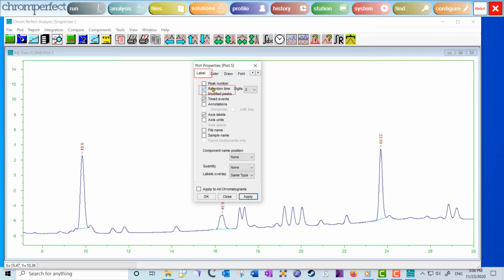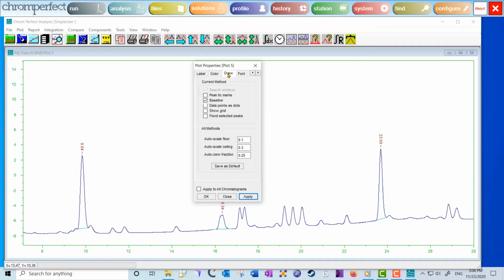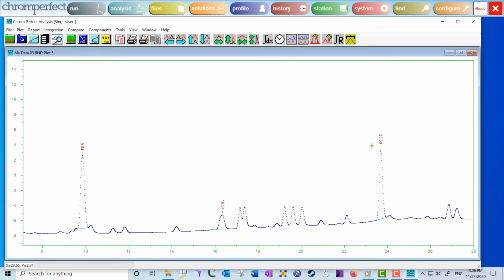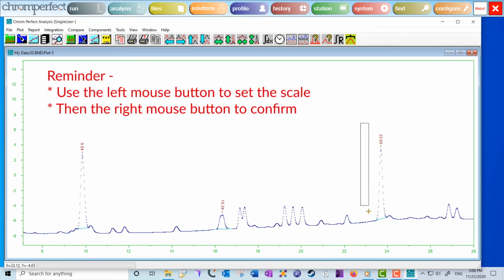Go to the Label tab. Make sure that the Retention Time box is checked. Go to the Draw tab. Make sure that the baseline box is checked and check the data points as dots box. Press the Apply button. The easiest method of changing the scale is by using the mouse, as we discovered in the Run program. Using your left mouse button, draw a box around the peak or peaks of interest. Move the cursor inside the box and click the right mouse button to confirm.